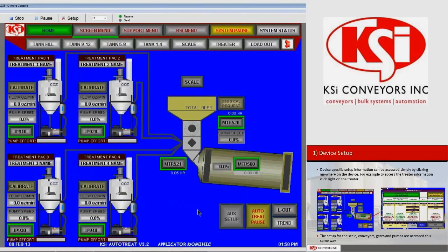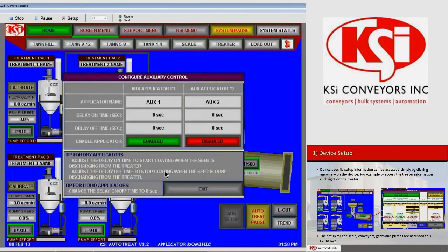The last thing on this page I want to quickly talk about is the auxiliary setup down here on the bottom. If we click this button, it opens up a window where we can set up 2 different auxiliary devices. On your AutoTreat system there's a connection panel where all your pumps plug into the bottom of that connection panel. It's going to be mounted somewhere near your treater. On the side of that panel are 2 120-volt plugs that you can plug 2 devices into, and those devices will be controlled based on these parameters right here.